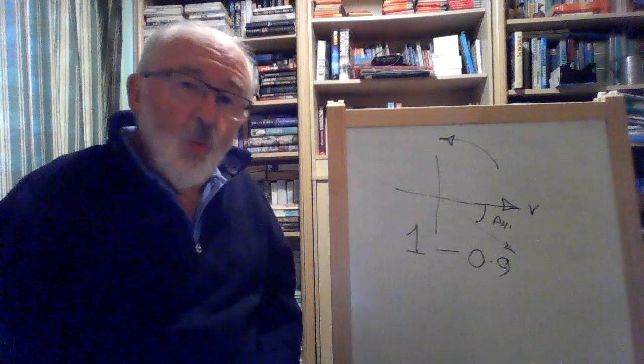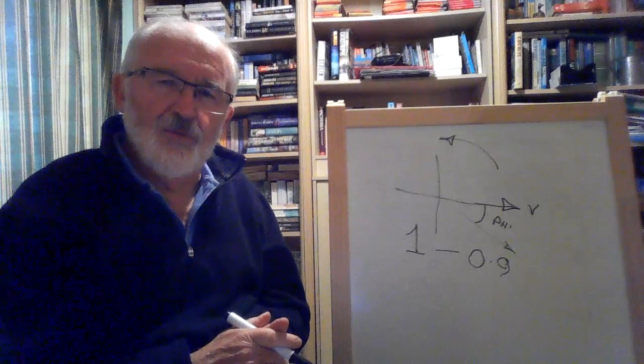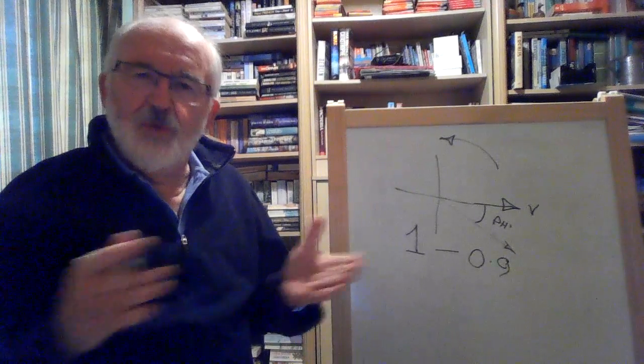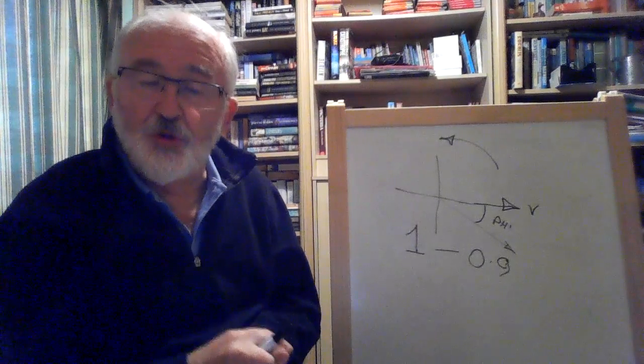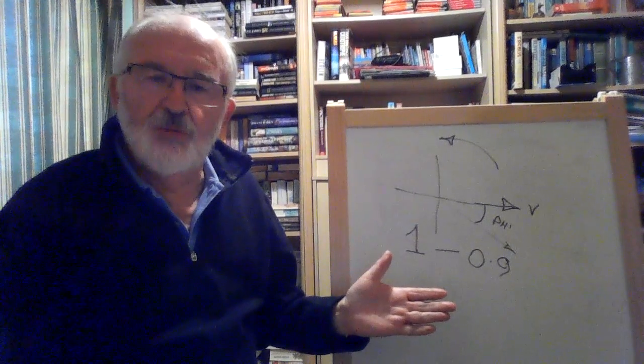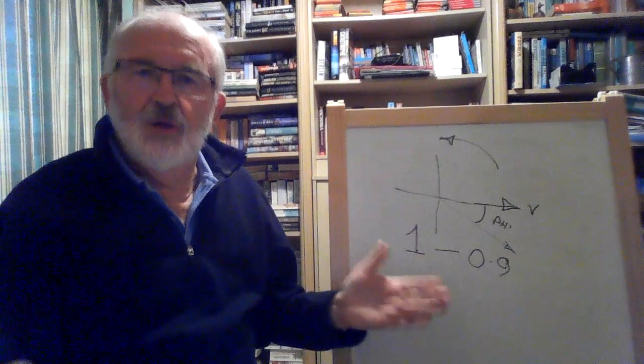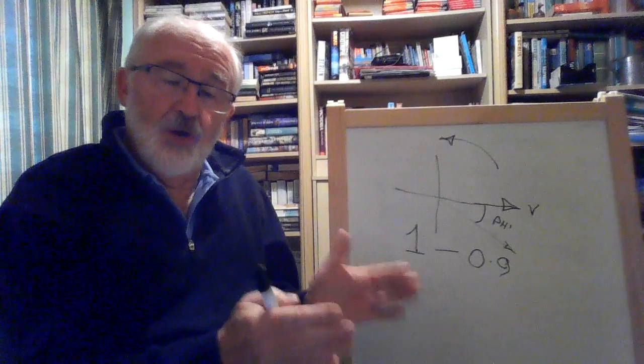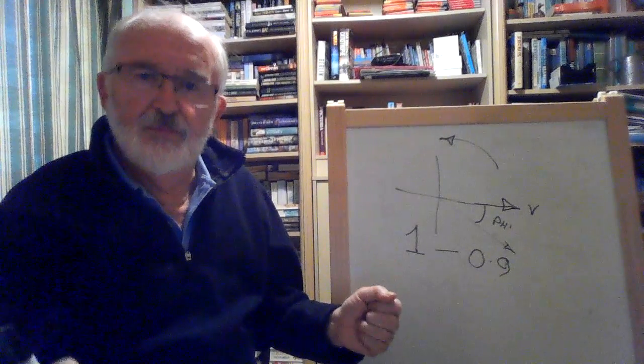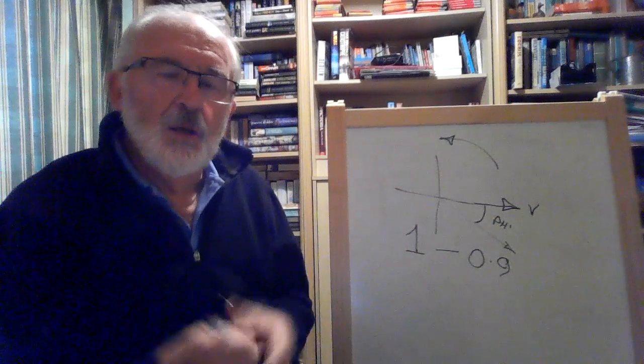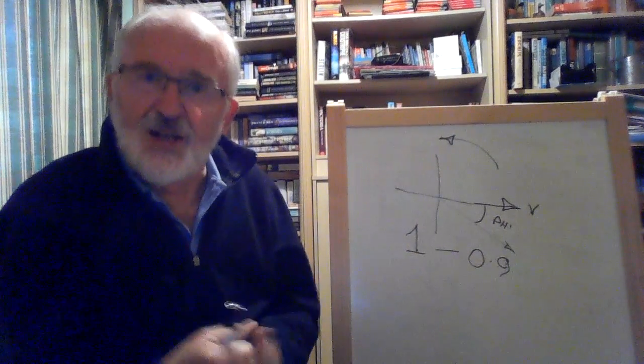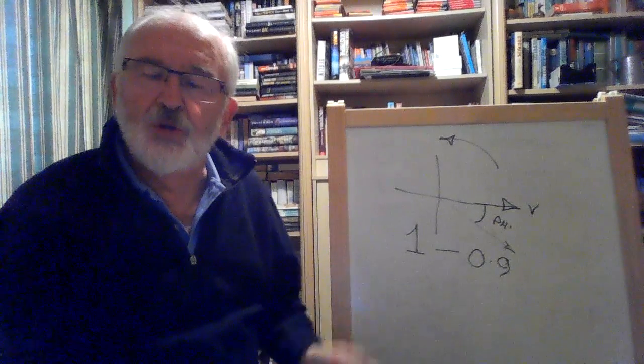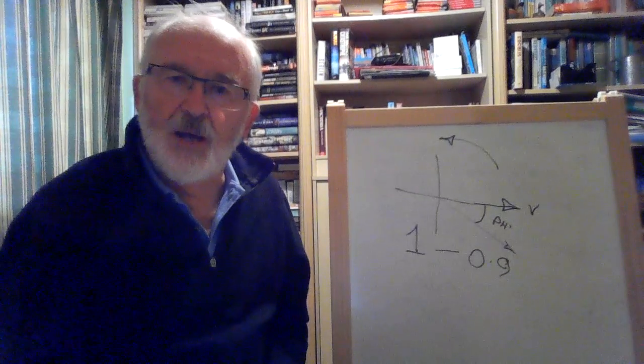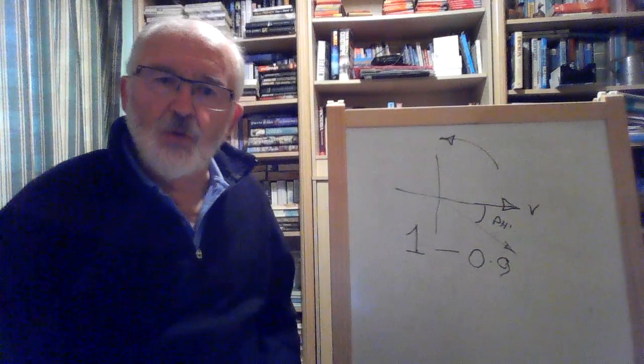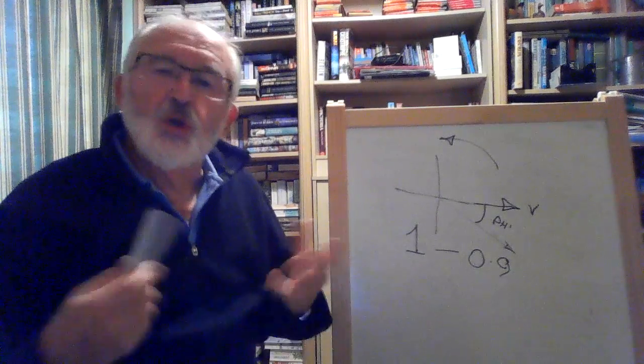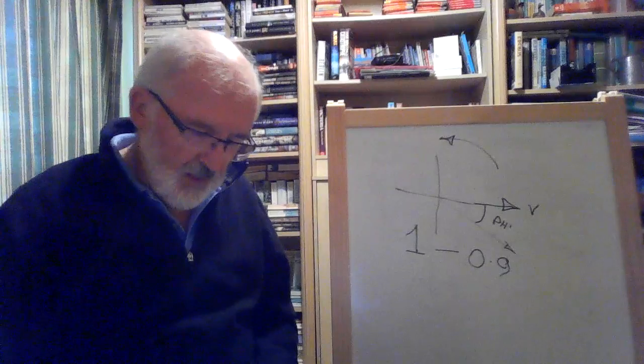Okay. Why do we insulate our pieces of equipment from the ship's hull? Well, if we didn't, as soon as we got an earth or a short, we would lose electrical power. That's not what we want on board a ship. If we were on land, yes, then it's there to protect personnel, people working in a factory or wherever it is. But on board, we don't want to lose our critical equipment. Example, the steering gear. Bump, it'd be gone. We'd black the ship out, knock all the power off, and we would lose control of the ship. So we don't want that to happen. So we have what we call an insulated earthing system.